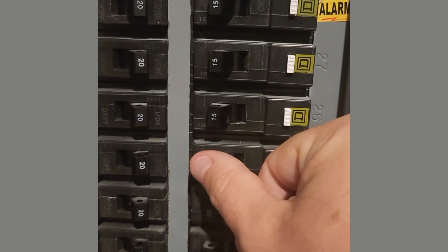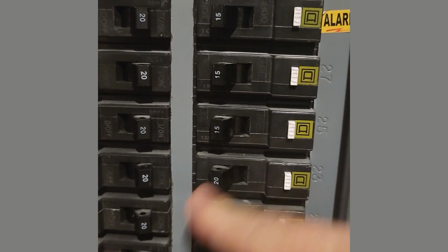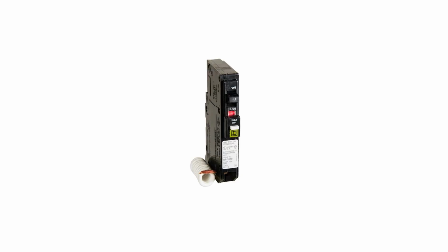Arc fault is a little different. It's designed to prevent arcs and sparks. The same thing can be true where you get nuisance trips. Maybe you plugged in a vacuum cleaner or something that caused a temporary condition that caused it to trip. You can reset it once. But if you have to keep resetting it, do the same thing. Unplug everything from all of the outlets in that area and see if it then resets. If it does, then it's probably that thing you had plugged in causing the problem, and it's very likely unsafe. You're going to want to replace that appliance or lamp or whatever it was that you had plugged in. If it continues to trip even with everything unplugged, then that's when we would suggest getting an electrician involved. Or you can always be safe and get an electrician involved right away. You just run the risk of them coming and unplugging a lamp and saying the lamp is the issue.